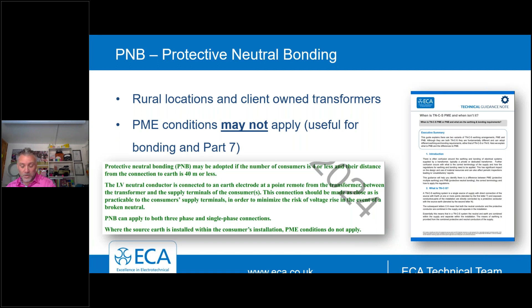So PNB bonding has advantages. Where the source earth is installed within the consumer's installation, so inside the panel board, PME conditions do not apply, and this can mean that TN-S earthing and bonding can be adopted. We have a great technical guide on this on our ECA website, and we're going to follow this up with a Technical Tuesday presentation. So that's a most welcome change.